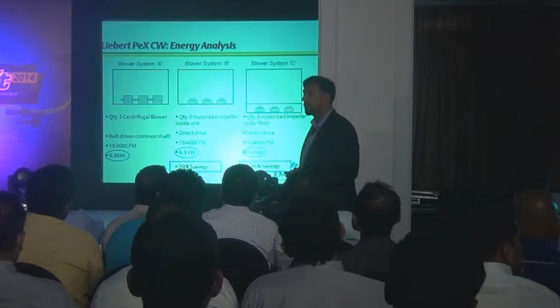Okay, we are now talking about the chilled water based systems. In chilled water based, we were the first one to integrate inflow EC fans with the ICOM controller. So what was the advantage of integrating inflow EC fans? You can see in this slide. The same fan inside the unit, this fan is brought down here below the false floor. You can see the power consumption difference at the bottom is about 16% compared to the second one to the last one. So this was the difference. This is just a lab result, which was for the same unit, same fan at same airflow at same static. This was the difference on the power. So we could save 16% by integrating the inflow EC technology in the units.